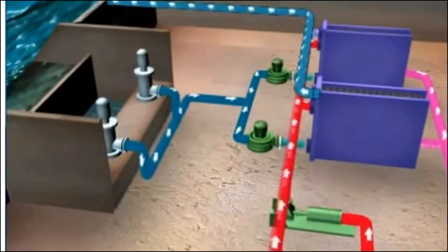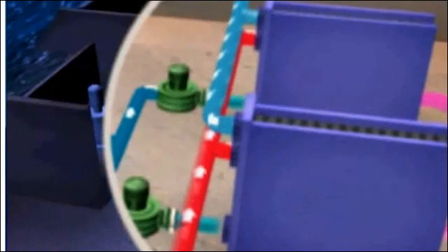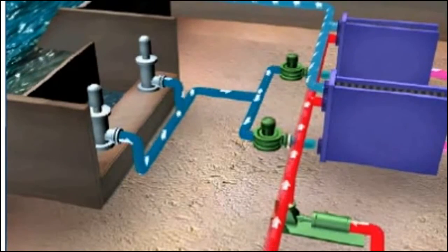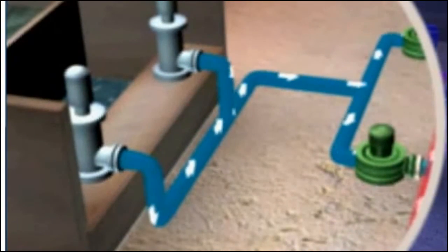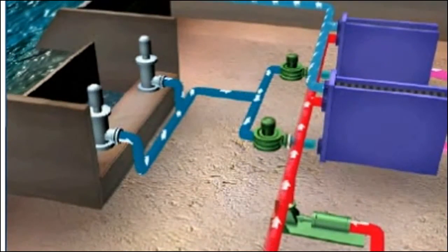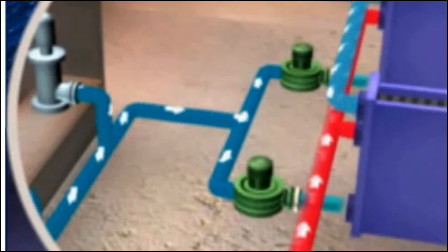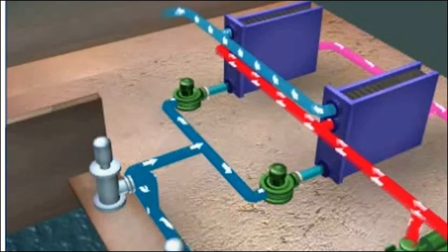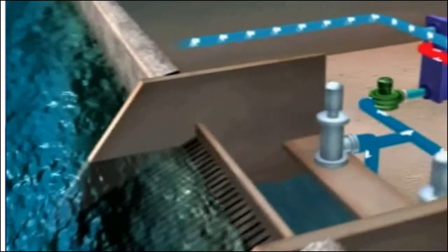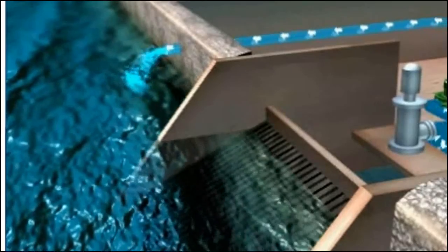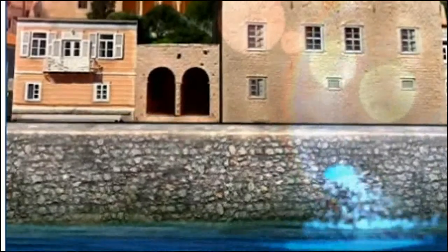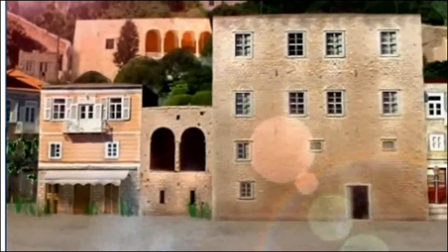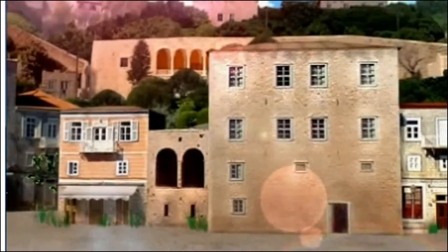The central municipal coolers consist of one or more plate heat exchangers that provide the necessary heat transfer surface. The seawater is pumped using submersible or surface sea pumps, and before it reaches the plate heat exchangers, goes through the necessary automatic cleaning filters. Finally, the seawater carries the rejected heat back to the sea, where with the help of undersea currents and sea breeze, it is naturally dissipated to the atmosphere through the evaporation process. The final stage transfers the cooling load to the atmosphere naturally, without consuming any primary energy and without increasing the atmospheric temperature.